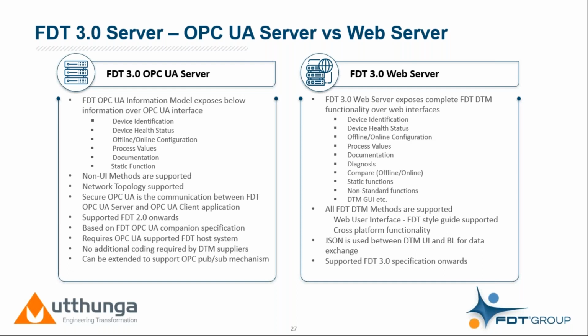With the FDT 3.0 web server, it offers much more than the OPC UA server, because the entire device functionality can be exposed via the web server. Apart from what's offered by the FDT OPC UA server, the FDT 3.0 web server allows common DTM functionality like compare, static functions, non-standard functions, and even complex GUI methods to be supported via the web server. This allows you to entirely recreate the web client remotely, and this web server concept is supported from FDT 3.0 onwards.